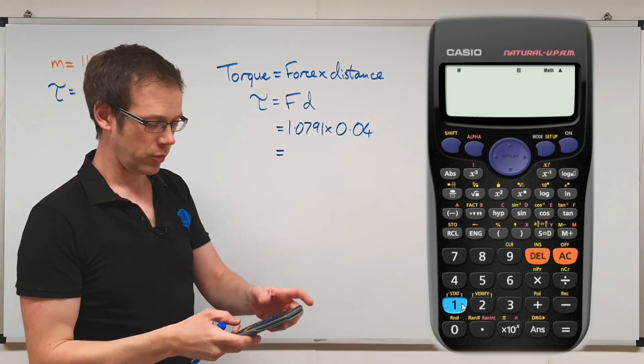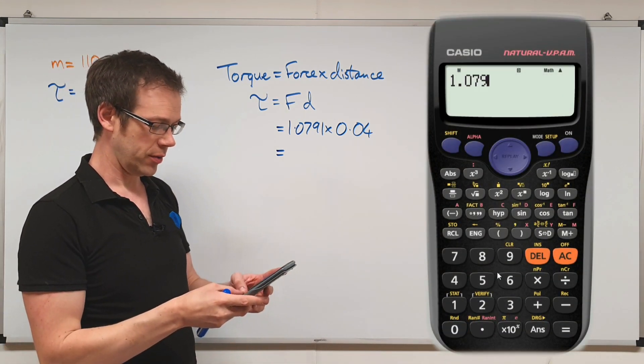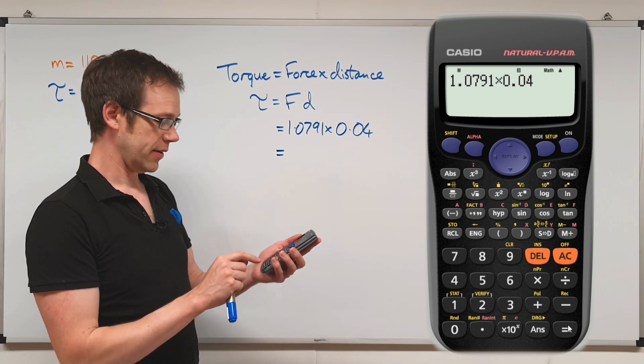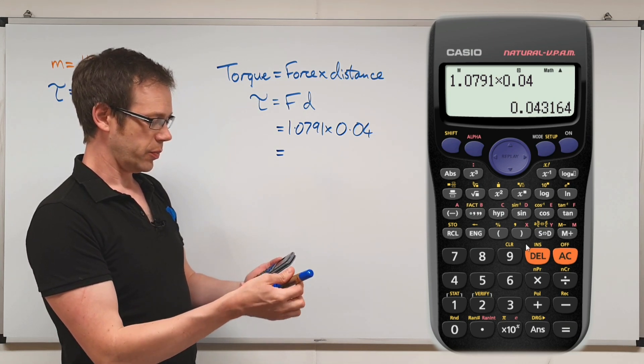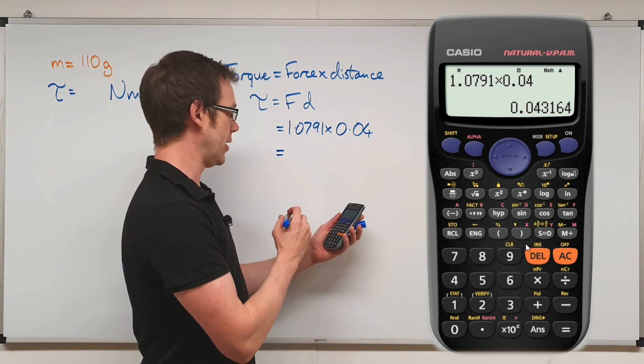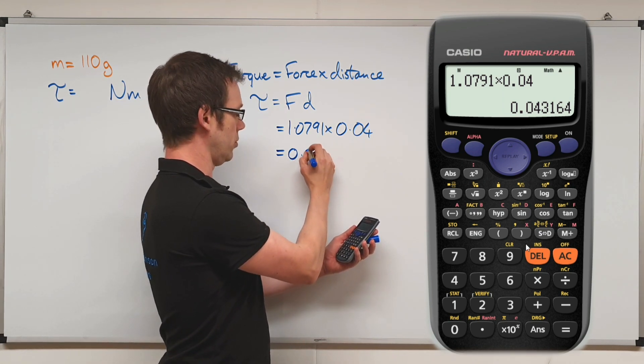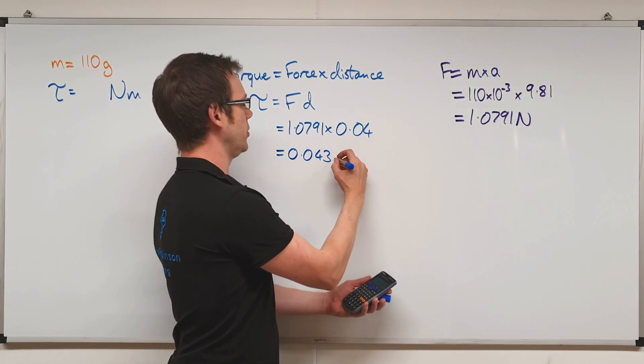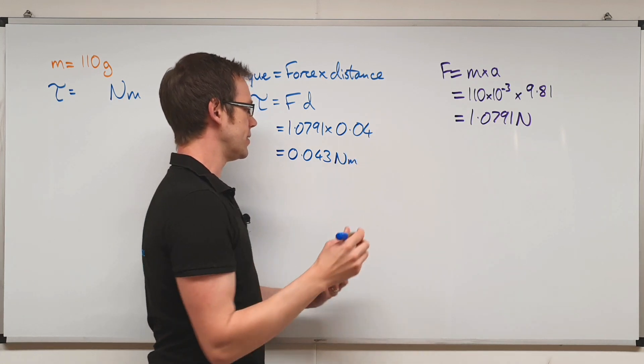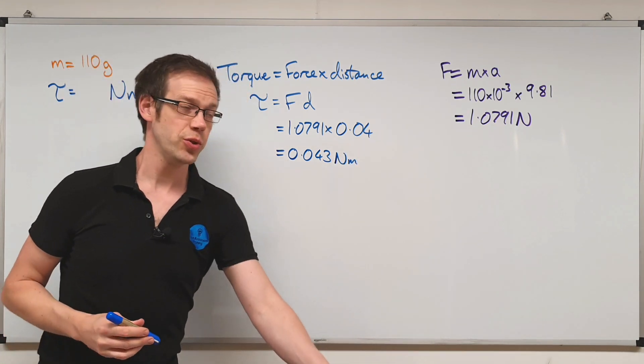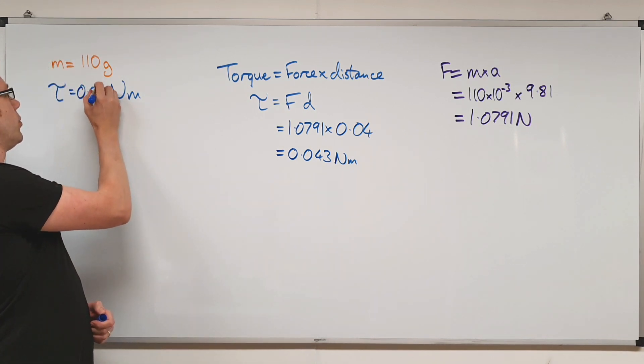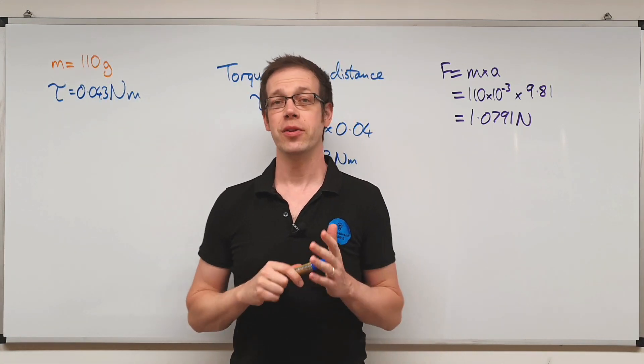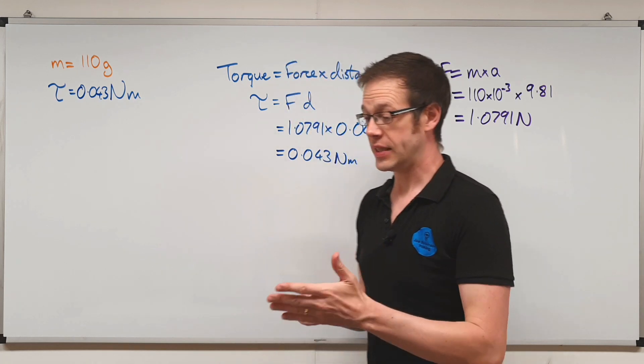Again, we'll just stick that into the calculator, 1.0791, and times that by 0.04. And that's going to give us an answer of 0.043—we'll round that off to three decimal places. So that's 0.043. And bear in mind here, we've got newtons and meters, so the unit that we've found there is newton meters. So in other words, this motor is producing a torque of 0.043 newton meters. So that's what we're looking at there. That's how we carry out the torque calculation for this particular motor.